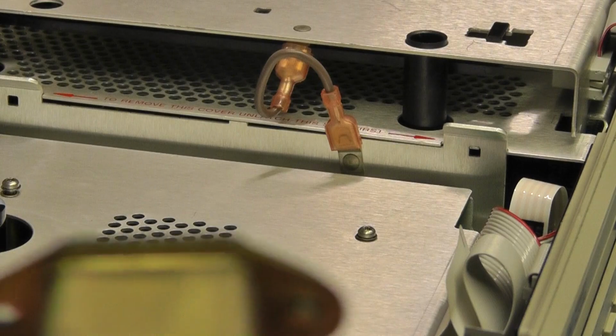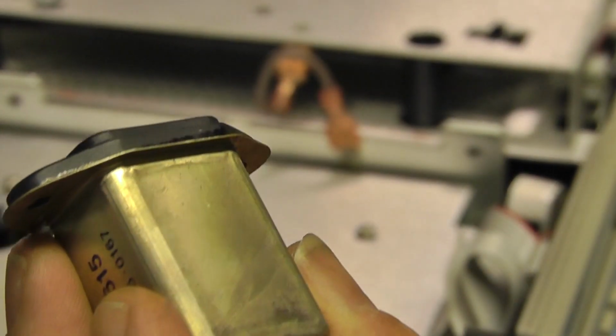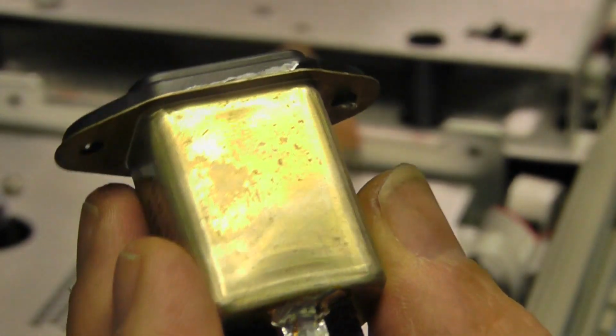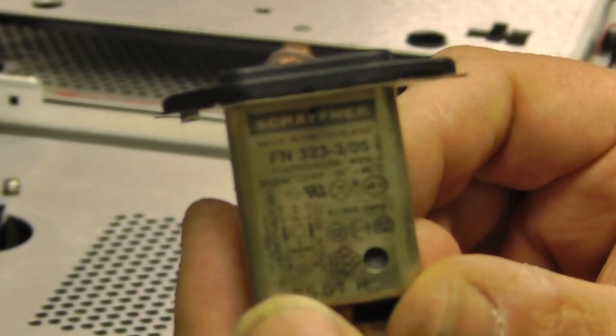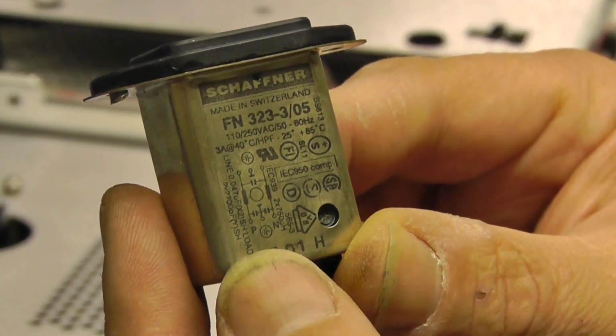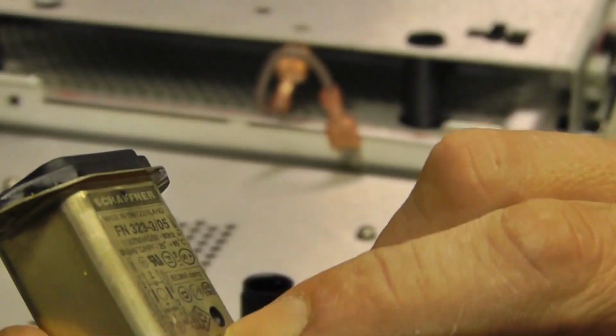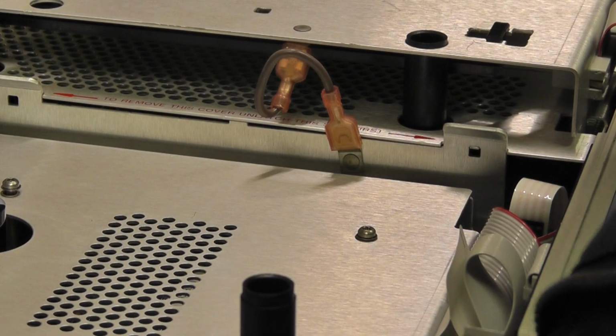Now what I'm going to do, for the meantime, is see if I can disconnect it, get it apart and dig out the filter. It's going to be stinky inside, and then see if I can wire it up. It's a Schaffner filter, and it's common for these to fail. Looks like there's a vent plug there that's sort of blown sputum everywhere, so let's see if we can get this thing apart and fix it.